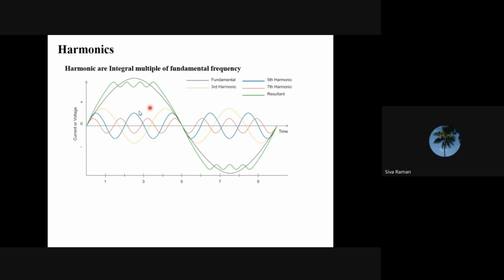So due to that, the fundamental frequency gets distorted. In this figure, the black line is the fundamental frequency. Let's consider it is 50 hertz. And it has three harmonic components: third order, fifth order, and seventh order. Third order means 3 times the fundamental frequency. Fifth order means 5 times the fundamental frequency in one cycle. So in this figure, the fundamental frequency is one cycle. In that, the third order harmonic will complete 3 cycles. The yellow line is the third order. Within one cycle of the fundamental frequency, it will complete 3 cycles. Similarly, the fifth order is in blue color. Within one cycle of the time period, the fifth order will complete 5 cycles.